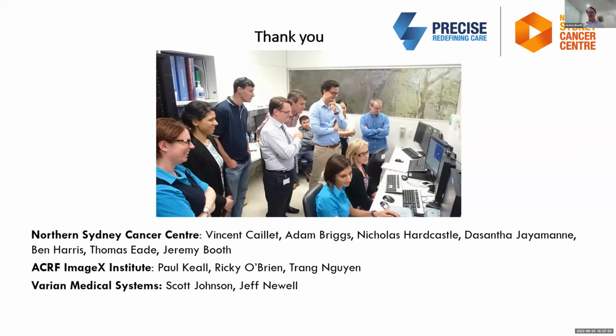Absolutely. So we had a research system implemented at our institution. It was the first one in the world. So we took great care and went over the top, if you like, doing everything three ways. If we had a commercial system, I think we would fall back on the same way that most QA has fallen, such that we do commissioning tests, and then monthly QA, and the patient-specific load would be greatly reduced down to almost zero.